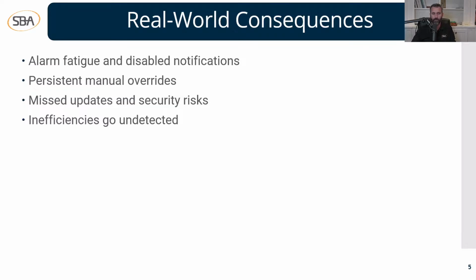You may have critical alarms that aren't being acknowledged. Go to the alarm log on a user interface - I've seen this during job walks when putting together proposals and estimates - and the alarm log would be flooding the system. There are alarms everywhere, maybe just notification alarms, sometimes critical alarms that have to be acknowledged before a system can run. A lot of these get ignored, and that's called alarm fatigue - there are just so many alarms we don't even know what to do with them anymore. Getting in there and cleaning those up is very important to maintaining your smart system.